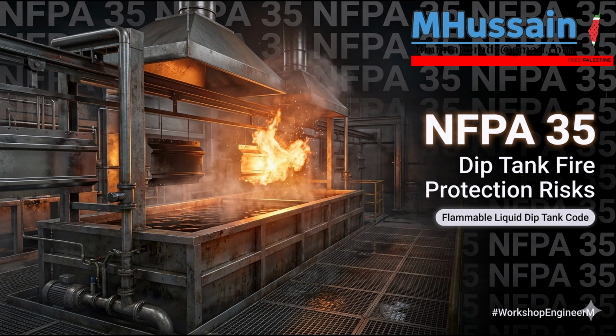Actual fire. Right. And there is a massive caveat here for process engineers. The volatility rules completely shift the moment you add heat. What do you mean? Well, if your manufacturing process requires heating a relatively safe Class 2 or Class 3 combustible liquid up to its flash point, the surrounding area instantly becomes a classified hazard zone. Oh, wow. So the chemical didn't even change? Nope. But by adding heat, you've transformed it into a Class I hazard functionally. Which completely alters how you have to build the facility around it.